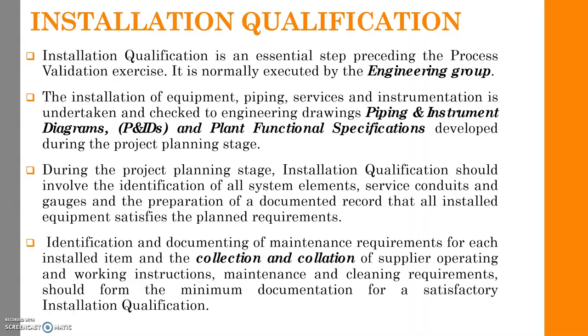Installation qualification should involve the identification of all system elements, service conduits and gauges, and the preparation of a documented record that all installed equipment satisfies the planned requirements. Identification and documenting of maintenance requirements for each installed item and the collection and collation of supplier operating and working instructions, maintenance and cleaning requirements should form the minimum documentation for a satisfactory installation qualification.